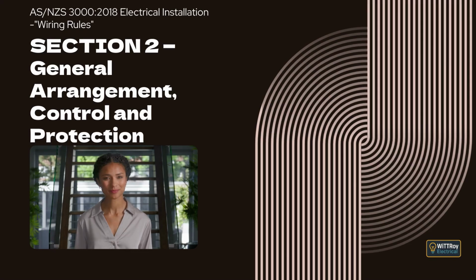2.3.2.2.1 General. This clause explains what an isolation device must be able to do. A device for isolation must be able to disconnect all active conductors of that circuit. A semiconductor device cannot be used by itself for isolation because it cannot guarantee a safe open state. The isolation device must be able to withstand any impulse voltage that could appear at the point of installation.